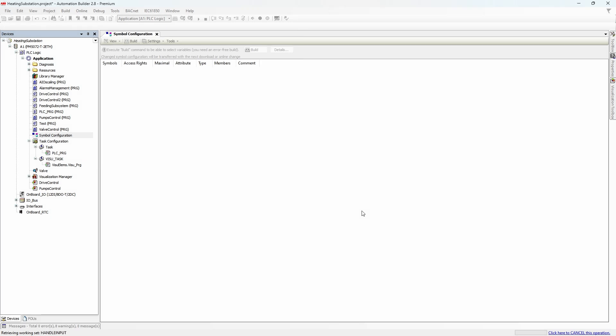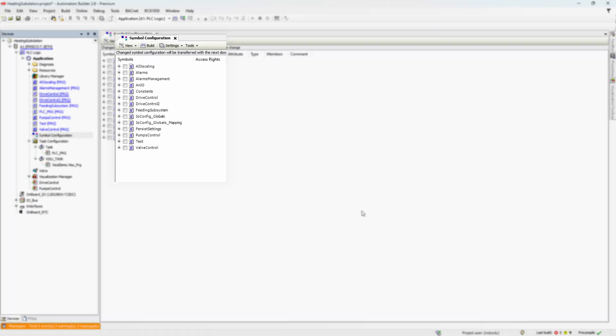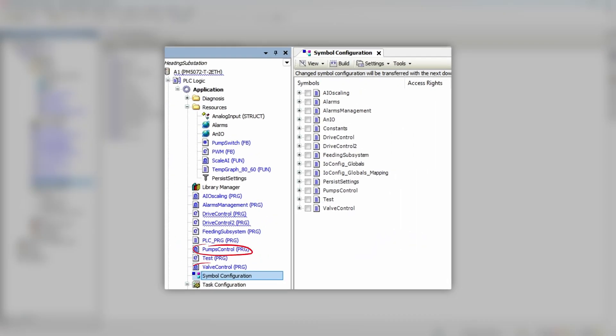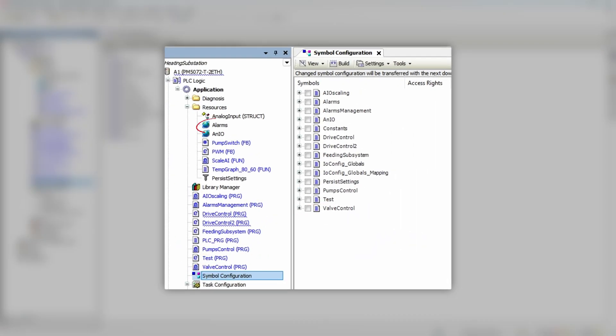That's because you need to build the project with no errors first. You can do it right here in the same window — just hit the Build button. After Automation Builder finishes the compilation process, in the Symbols column you can see something from the project. Basically, every program POU with internal variables or global variable list will be represented here, like pumps control and valve control programs, as well as alarms and persistent settings lists.